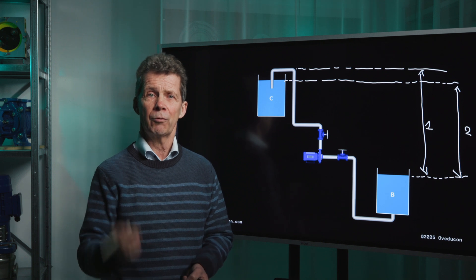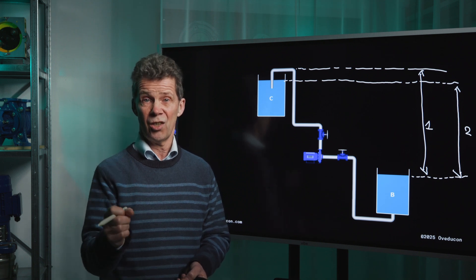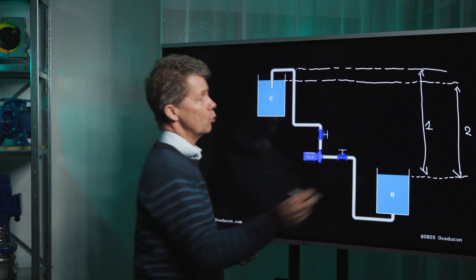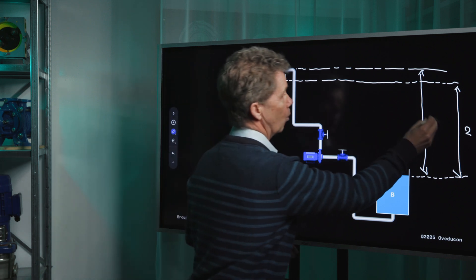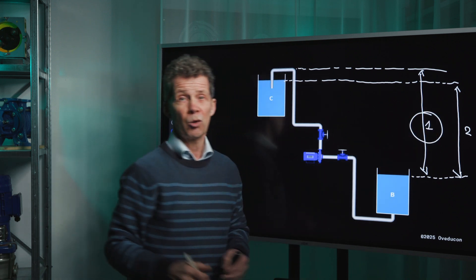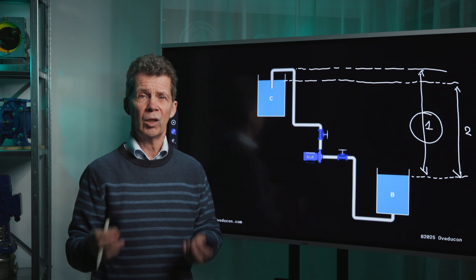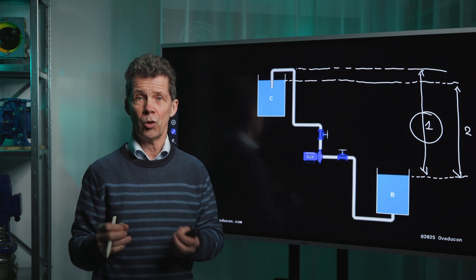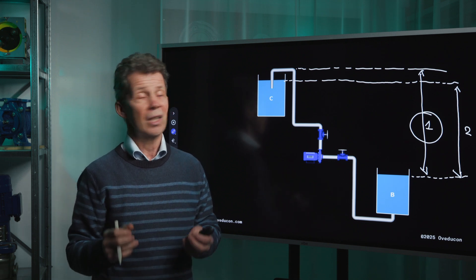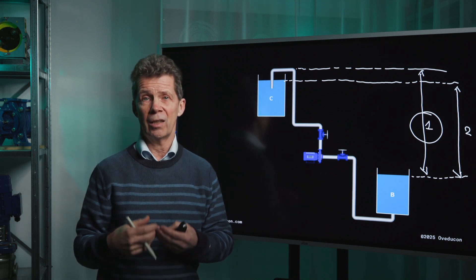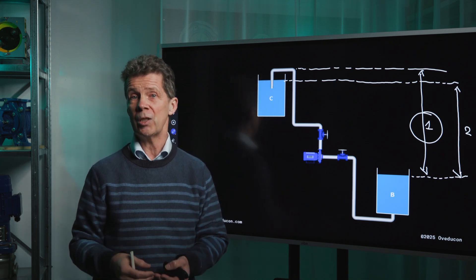For your centrifugal pump sizing process you have to use the first situation — the empty discharge line — because you always have to work for the worst case situation, and that is when your discharge line is not yet filled with medium. Now you know what static head is.